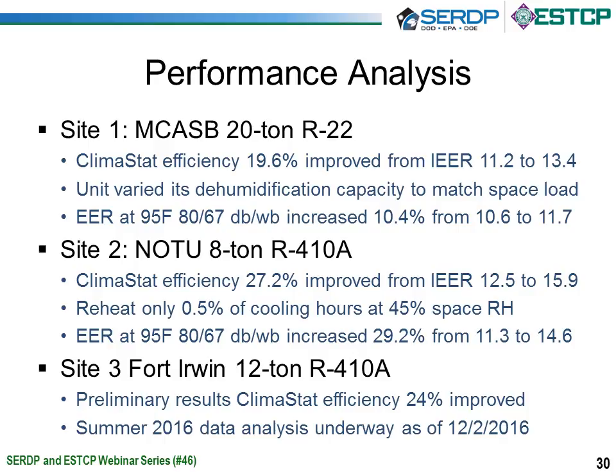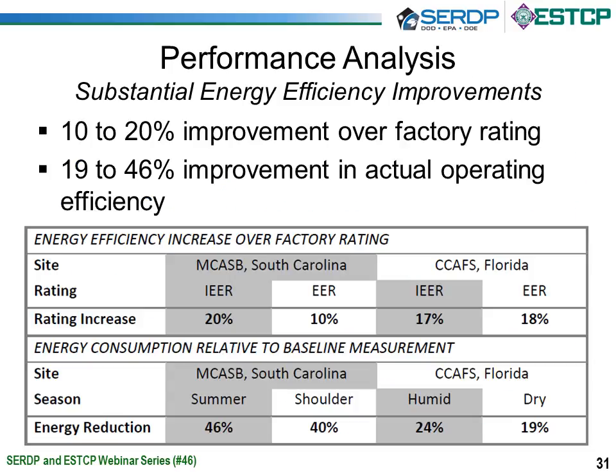Site 3, we're still analyzing data. Preliminary results show 24 or 26% improvement at that site. Key here is what we are comparing our efficiency against, or versus what. So we can look at improvement over factory rating, or we can look at improvement over the actual operating efficiency. And typically the field efficiency of the unit installed in the actual climate we found was a little bit less, or significantly less, than the factory rating. So that's why we gave 2 different percentages here, versus factory rating and versus what the actual efficiency was.